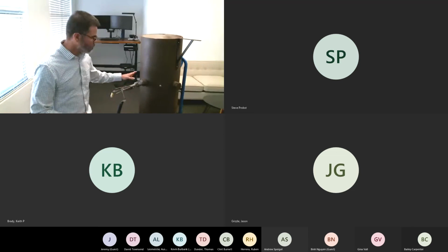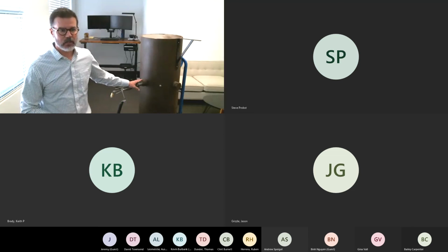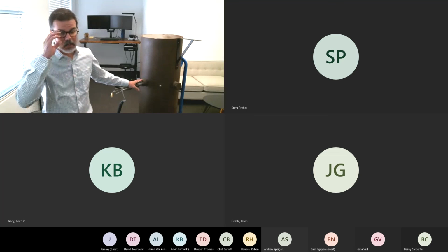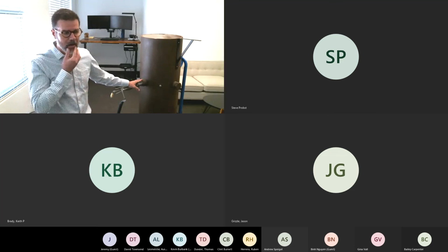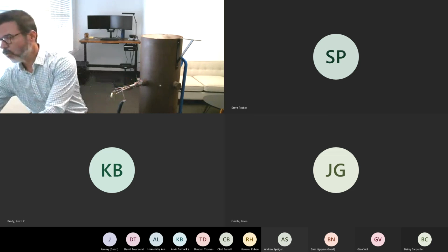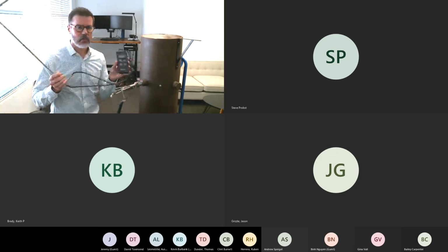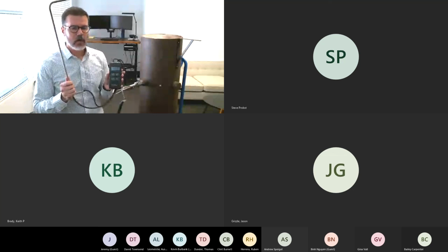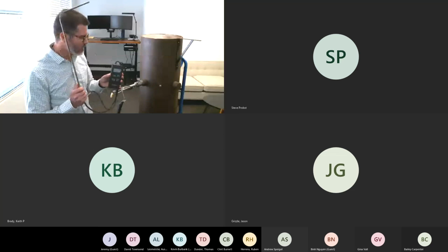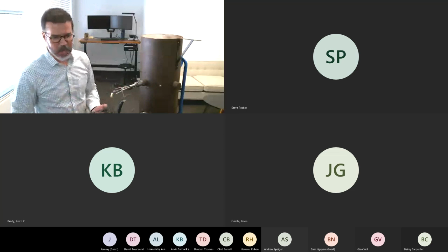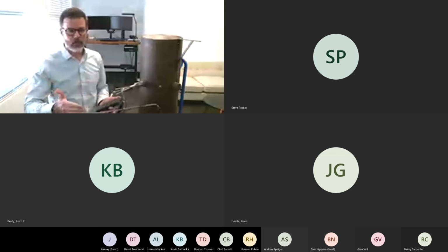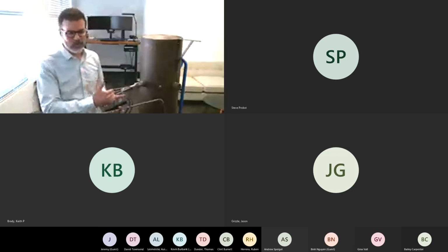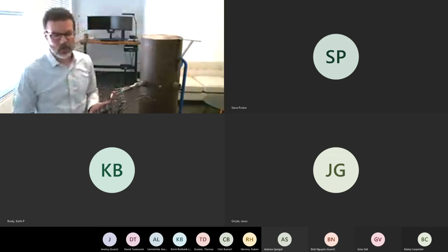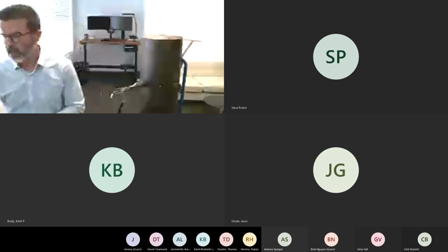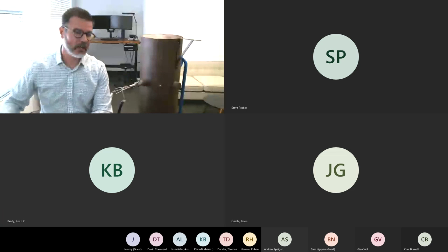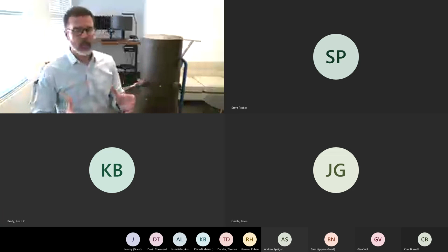So as you can imagine, if you're doing this procedure, it takes a little time at the stack to get all of these readings. We use digital manometers, getting from the digital manometer to a fluid or an oil gauge based manometer at the end of the day.